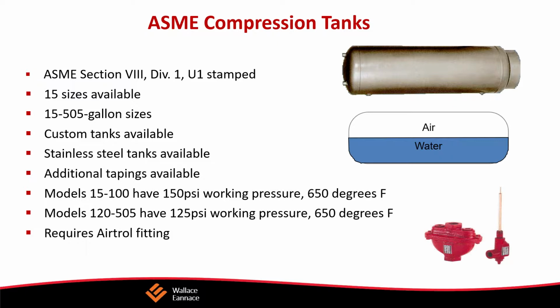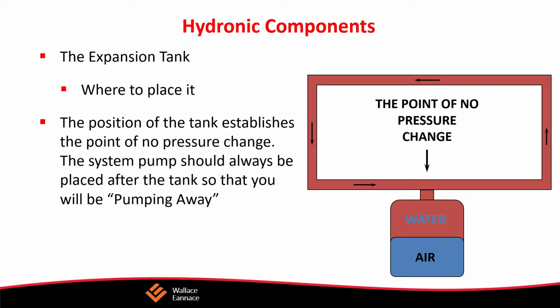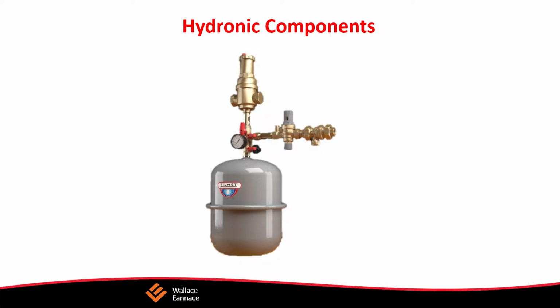And when it comes to sizing, there are a number of ways to do it. Basically, Bell & Gossett has a program that you can use, or, in smaller systems, you can just use this simple chart. This chart assumes a fill pressure of 12 psi, relief valve set at 30 psi, and average system temperature of about 200 degrees F. If the temperature is lower, you're probably going to have a smaller tank.